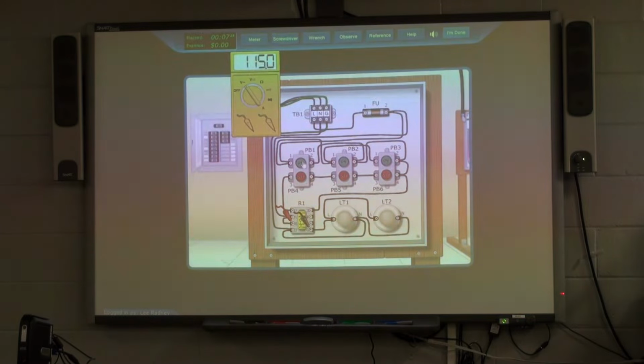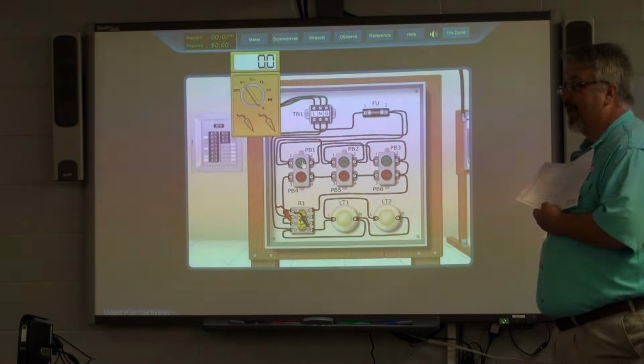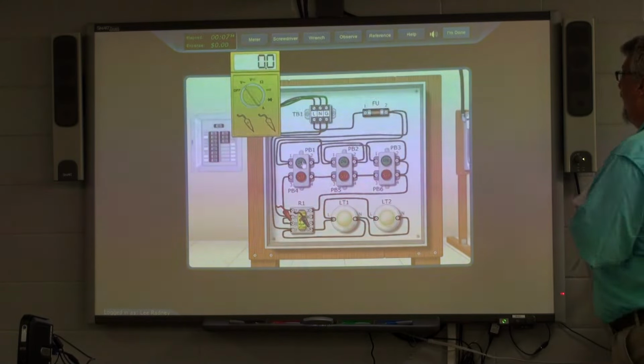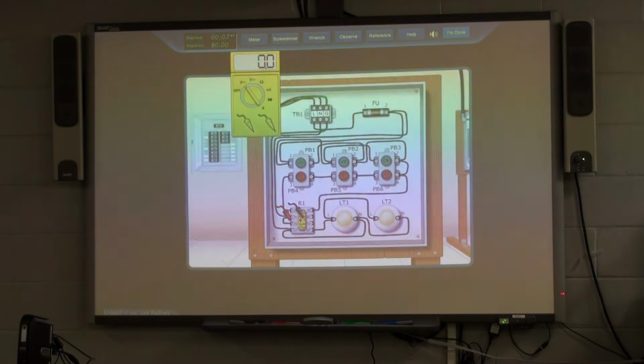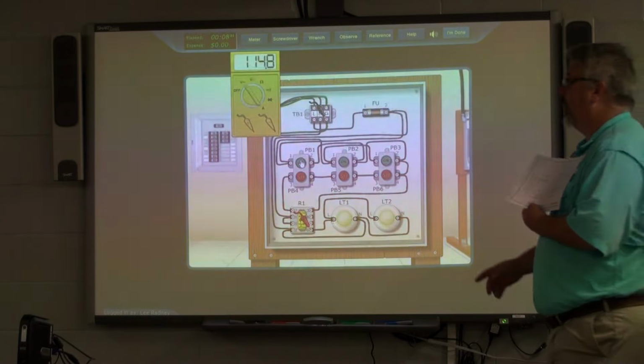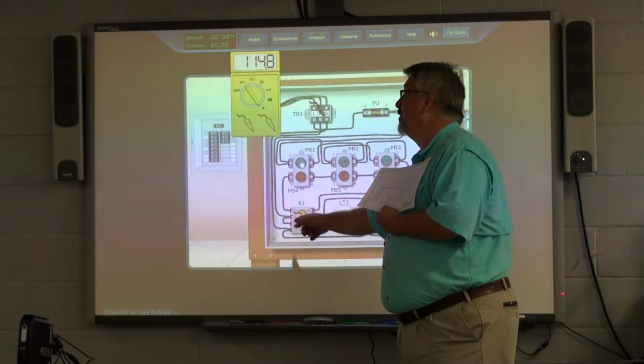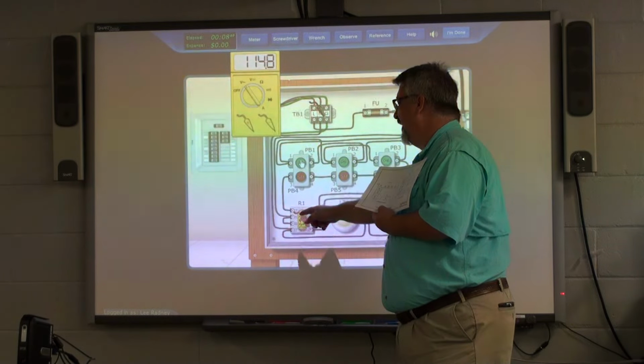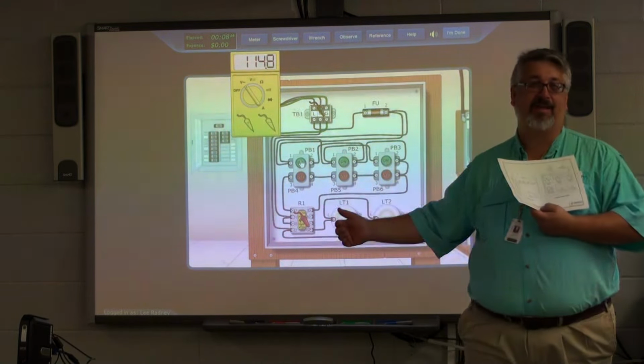Let's see if that happens. So yeah, sure enough, we are now at the same potential rather than the difference of potential. And now, relative to ground, both pin 8 and pin 6 will read 115 volts. But if I turn it off, pin 6 doesn't, but pin 8 does. And the only way I can get pin 6 to be 115 volts relative to ground is to make that normally open contact close. So what we did was hand off the 114.8 volts that was on pin 8 over to pin 6 and turned on our lights.